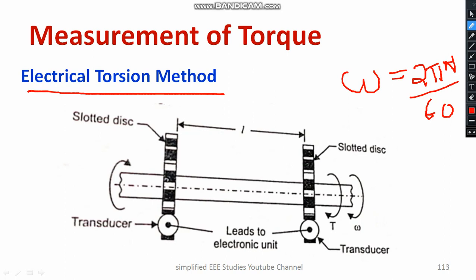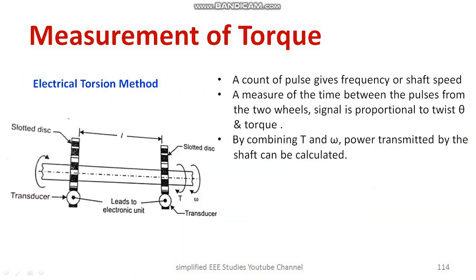The distance between two discs is the gap L. With the help of the slotted disc, you count the pulses with respect to rotation, and this count is fed directly to an electronic device. The count of pulses gives a frequency or shaft speed. The time between pulses from two wheels is proportional to the twist theta and torque.